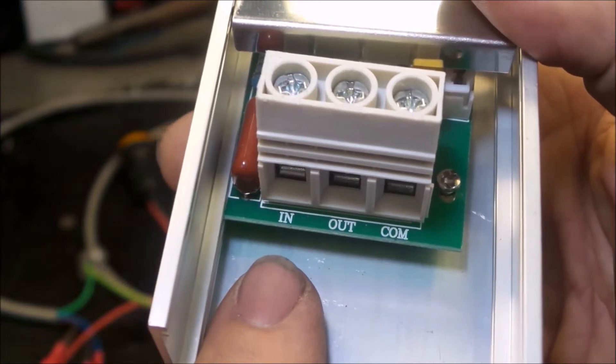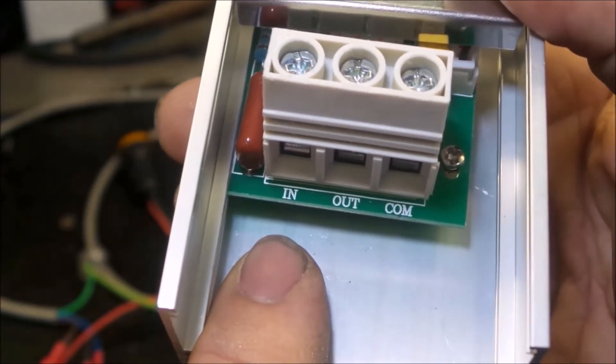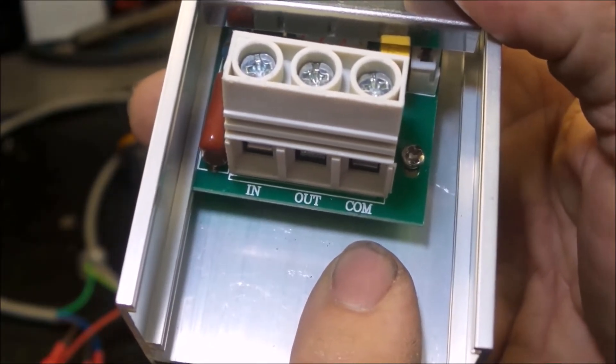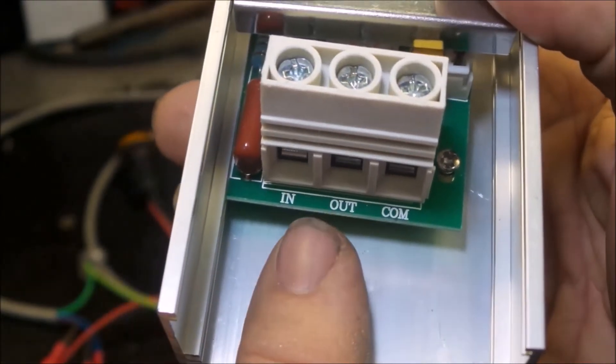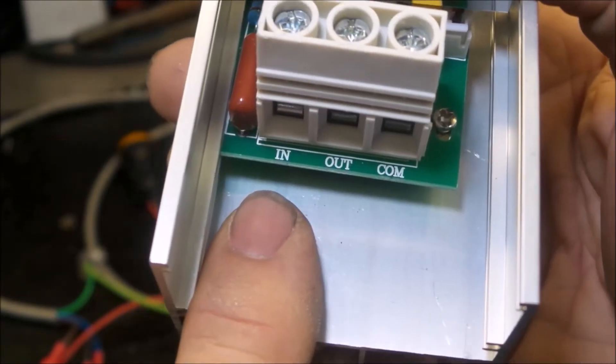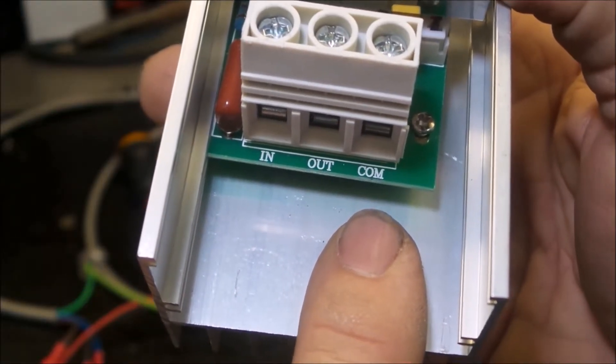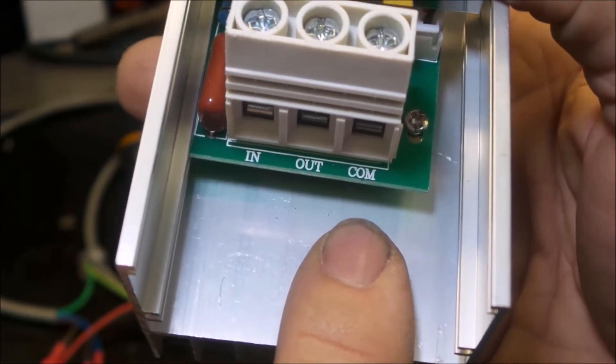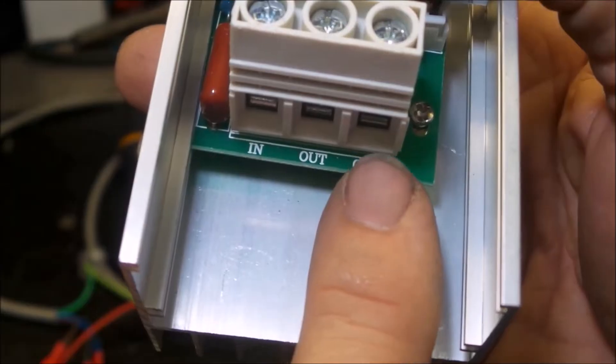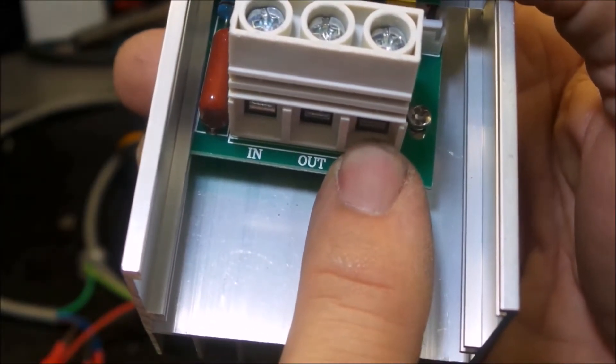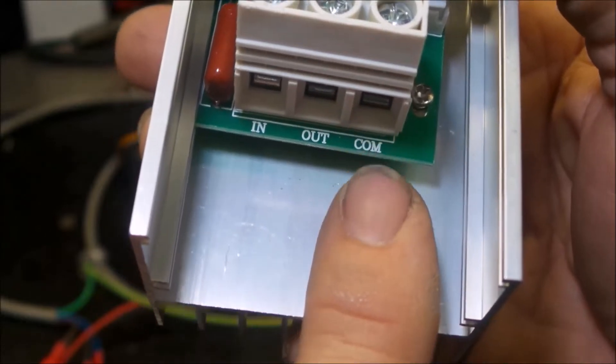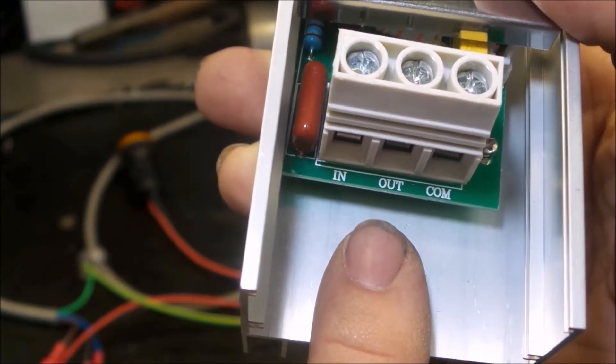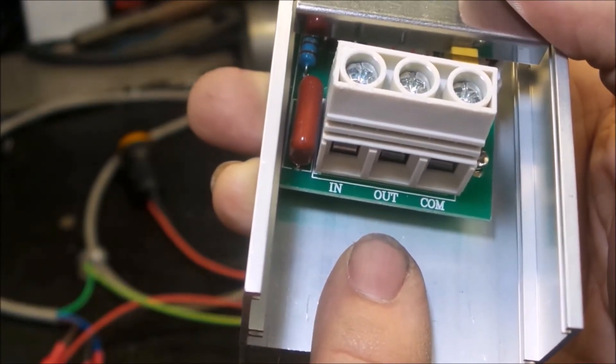In is your mains active in. So either the red or the brown wire. Comm is your neutral connection. Now this is your neutral in and out. And out is your active out. So you've got active in, neutral in, active out, neutral out. So there will be two neutral wires going into the comm connection. One is the AC input and the other is the AC output on the neutral side. And then active in, active out. I'll get some wires in there so you can get a better idea of what I'm talking about.